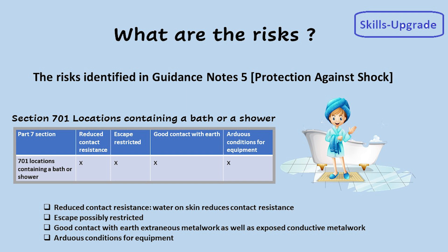Reduced contact resistance due to the skin being wet. Escape restricted by the confines of a bath, bathroom, or shower cubicle. And good contact with earth, which could be extraneous metalwork as well as exposed conductive metalwork. Also, equipment in a bathroom has to be suitable for its purpose due to the conditions in there, such as moisture.